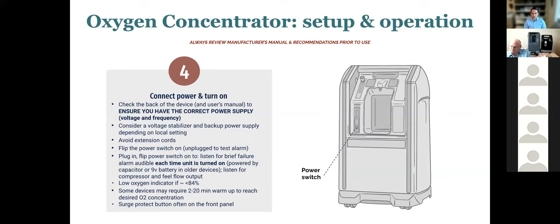Each time the unit's turned on, an alarm should sound, but it should silence itself automatically. So listen for that to take place. Also listen to make sure the compressor comes on. It shouldn't be subtle. You should hear the compressor. You should also feel flow coming out of the device when you open the flow meter. So those are just a few basic checks to get out of the way.